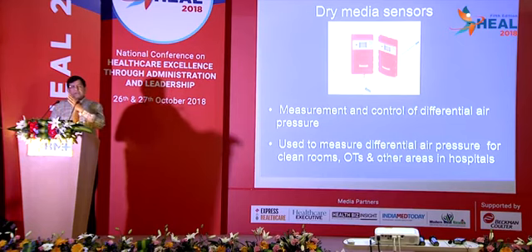Operation theatre zoning is not only created by the design of the operation theatre, but also it has to be supported with the HVAC system. This most sterile area has more pressure: in operation theatre it should be 24-25 pascals, in the clean corridor it should be 14 pascals, and in the protective area it should be 5 pascals. Only then will the air flow from the OT to outside, and this can be done with the help of dry media sensors. So with integration of the building management system, all the above parameters can be controlled or manipulated from the control room over a dashboard. You don't have to go anywhere else.